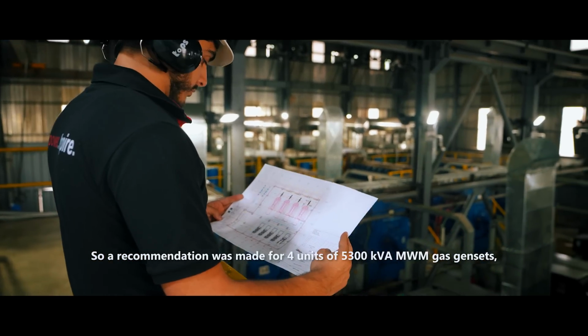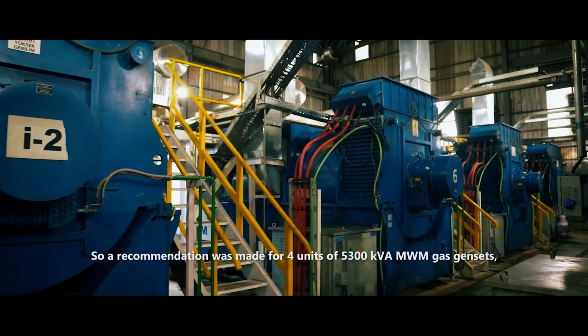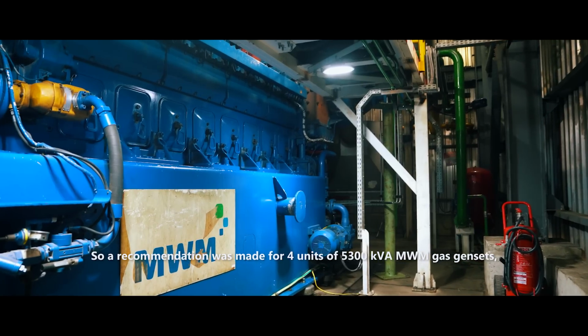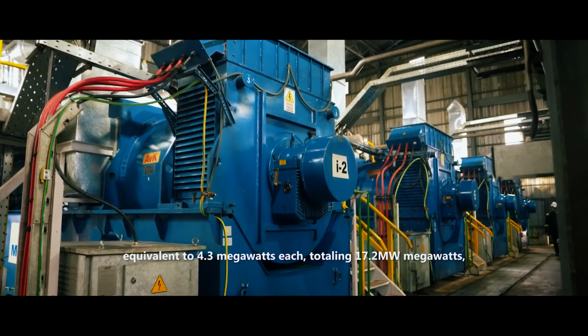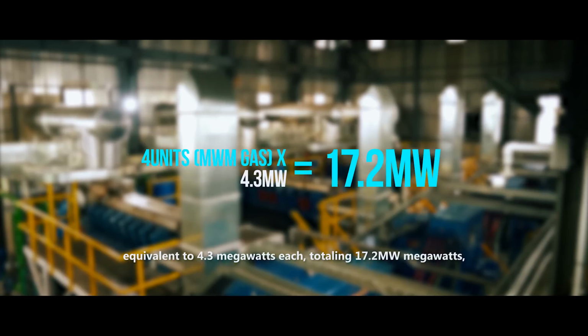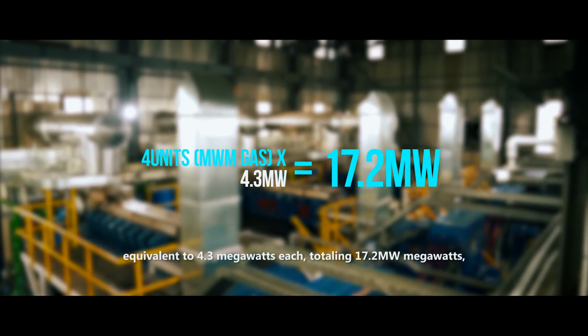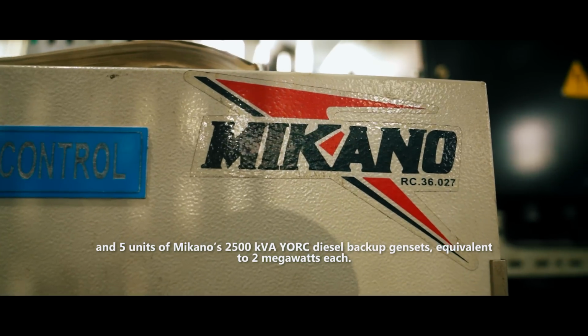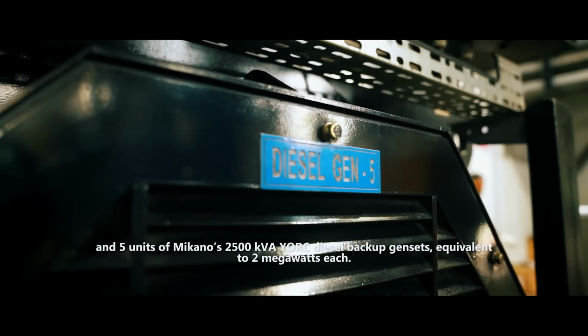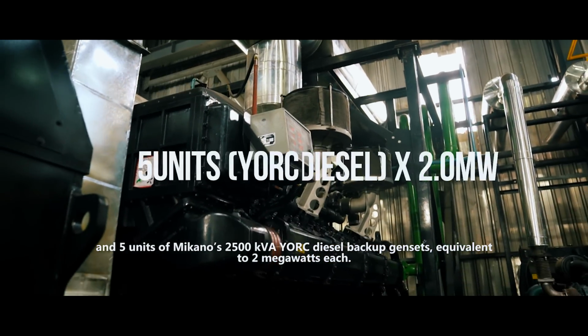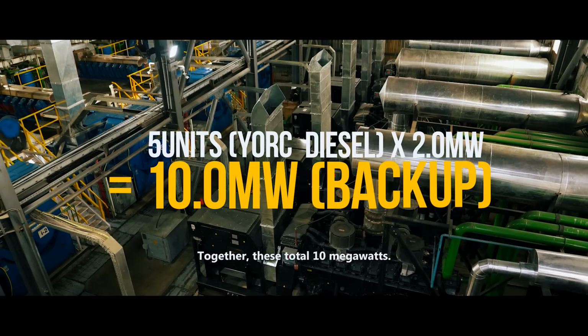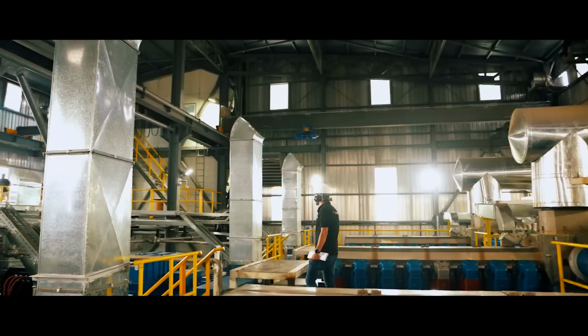A recommendation was made for four units of 5,300 kVA MWM gas gensets, equivalent to 4.3 megawatts each, totaling 17.2 megawatts, and five units of Mikano's 2,500 kVA YORC diesel backup gensets, equivalent to 2 megawatts each. Together, these total 10 megawatts.